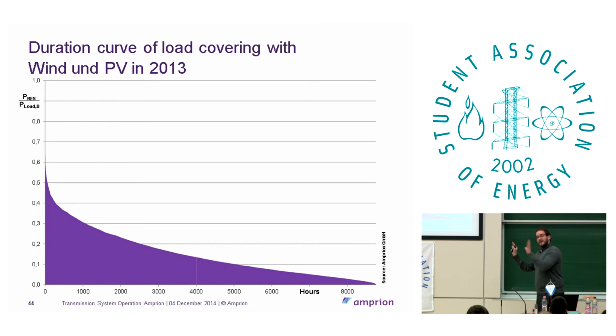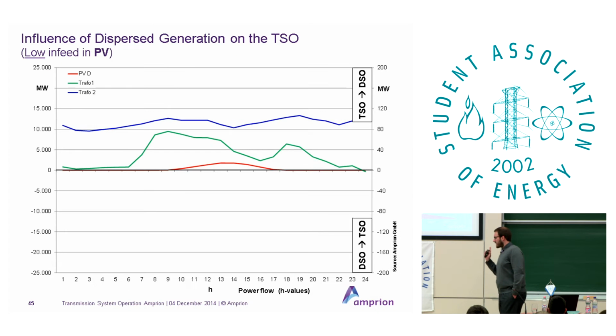So, enough of this—let's move to another challenge. As I mentioned before, the distribution of PV generation in Germany is concentrated mainly in the southern part. Now we're facing situations where, from time to time, there's a load flow from the lower DSO grid up to the higher TSO grid.